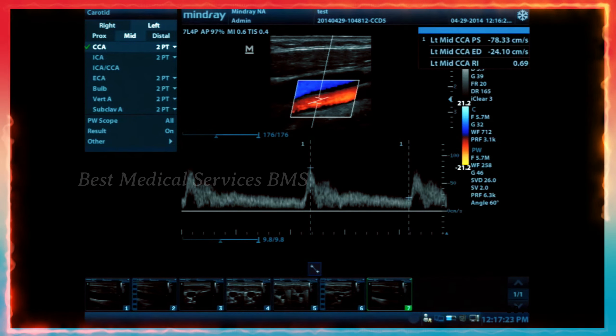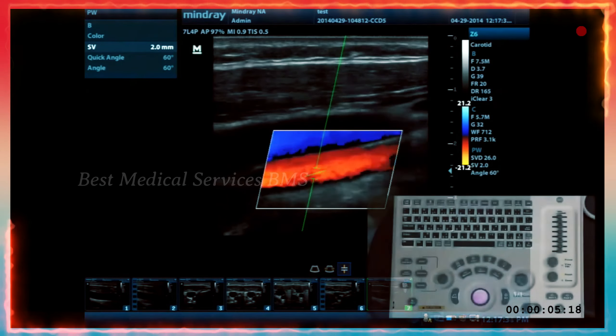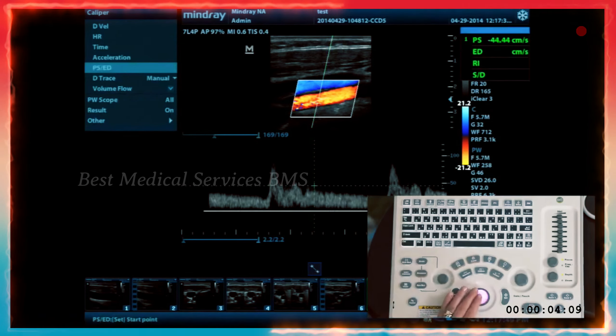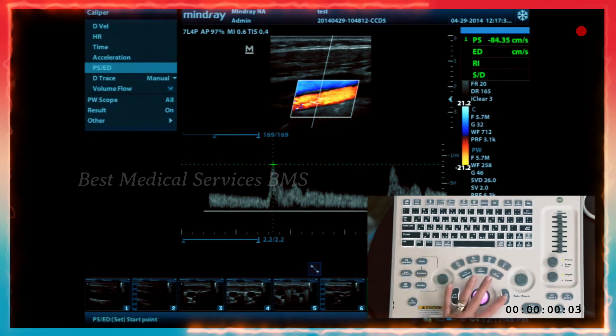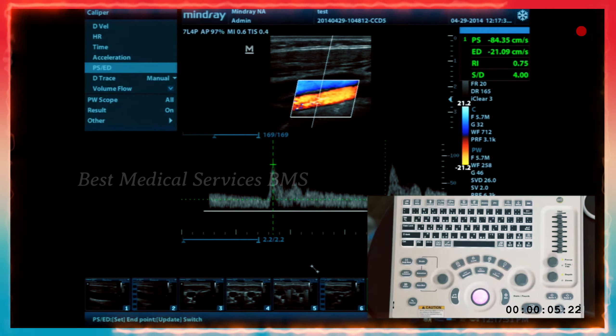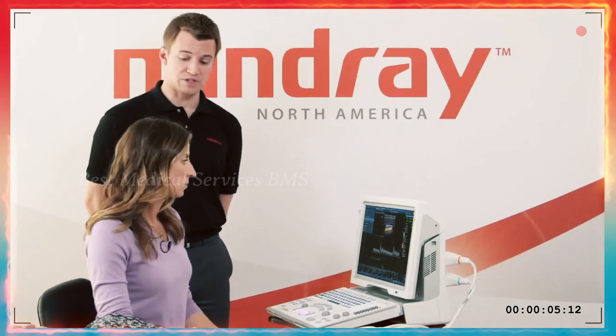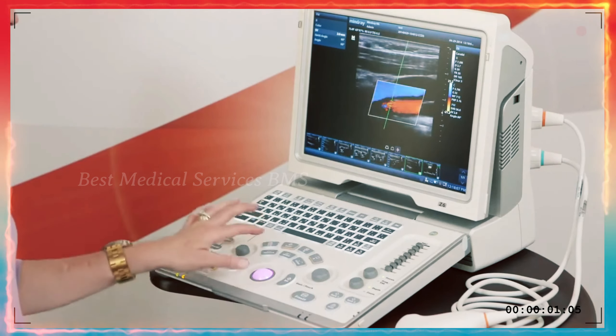If you freeze, you go back to live imaging. Now if you hit the caliper button while in a mode, you'll get a more generic list of things — you won't see vessel segments or right/left/proximal/distal. What you have is velocity, heart rate, time, and those menu options. That's fine if you want to take a measurement that isn't part of your calc package. That is the difference between measure and caliper: measure gives you the right calc package for whichever exam preset you're in, whereas caliper is a more generic measurement.